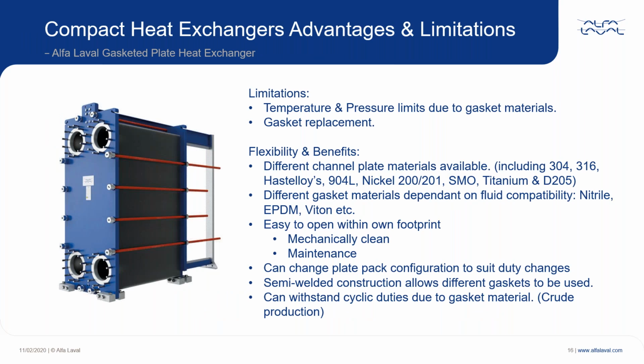So limitations: pressure and temperature limits due to gasket materials are probably, compared to shell and tubes, one of the two biggest. We are limited to 180 degrees with Viton gaskets. We are developing something a little bit higher, but that's only 200. And the standard gasket range, the big units go to 30 bar. If you go to semi-welded, you can go up to 55, 60. And then being a unit with gaskets, they can wear through time and they need replacing. But then the exchangers are easy to open.